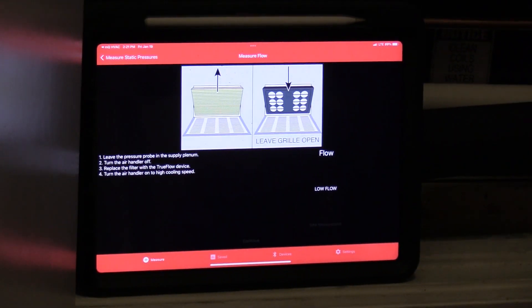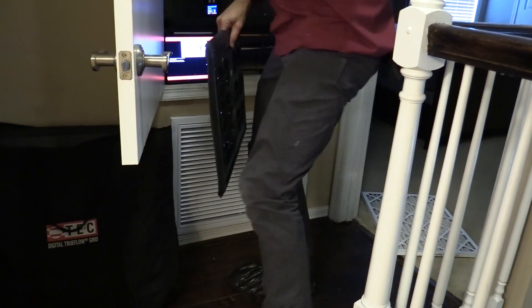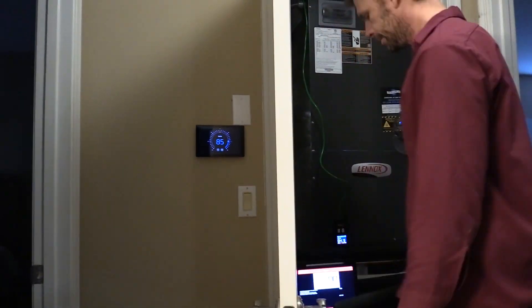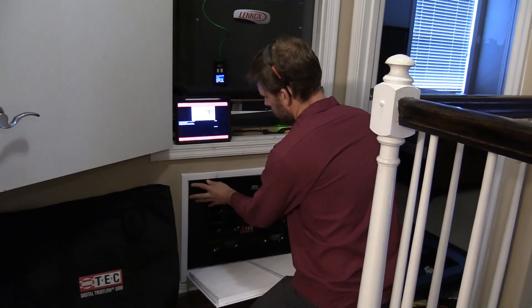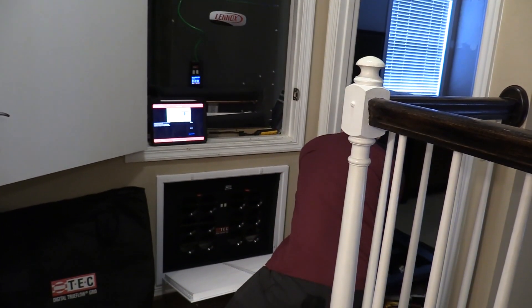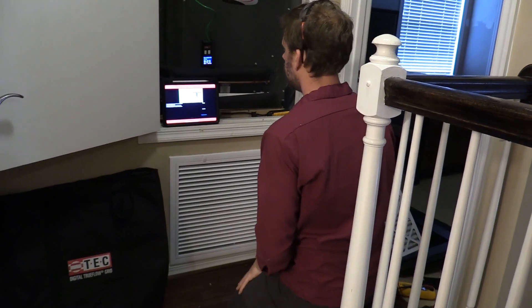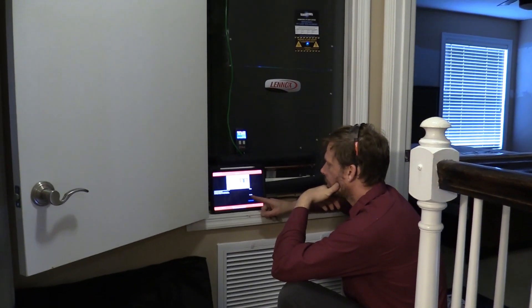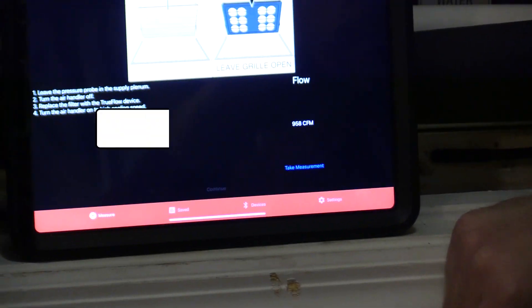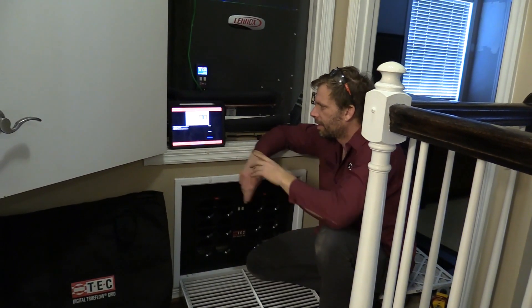Next, we replace our filter with our TrueFlow Grid. All the steps include turning off system operation, so I've got to make sure the unit shuts off, and then have the grill the right size, which is my 18x24. Put the grid in, in place of the filter. Turn the air handler back on high cooling. As the fan's revving up, it's giving us the actual CFM. I've got it in place, turned my air handler back on, and now I'm letting the fan rev up to full speed.